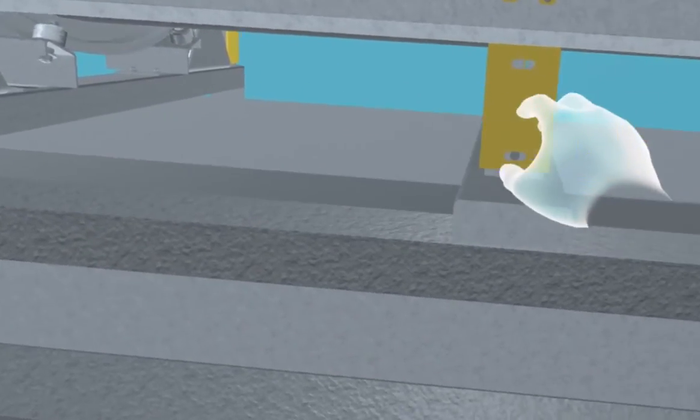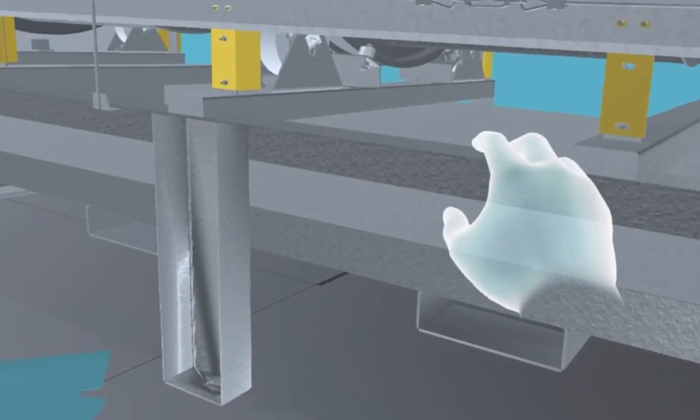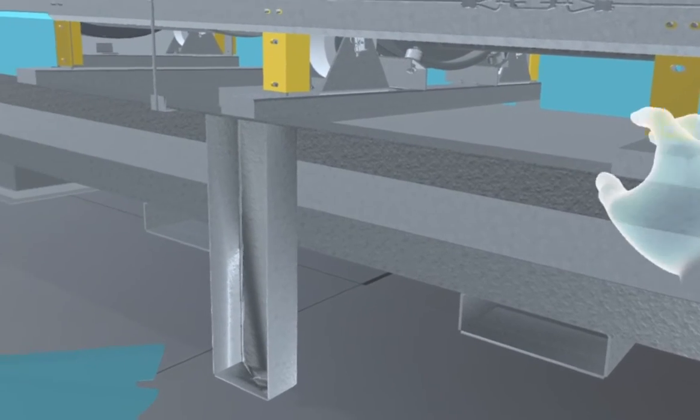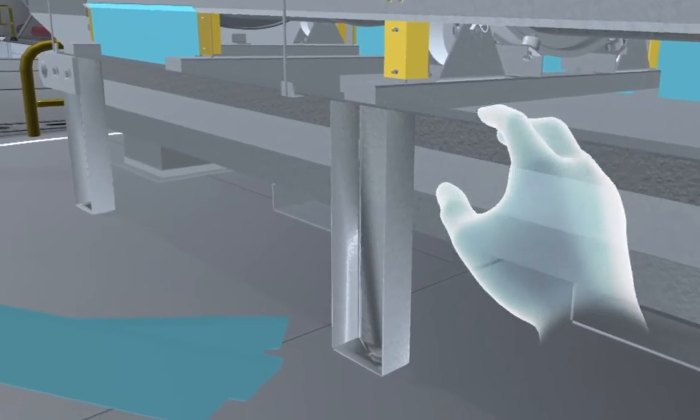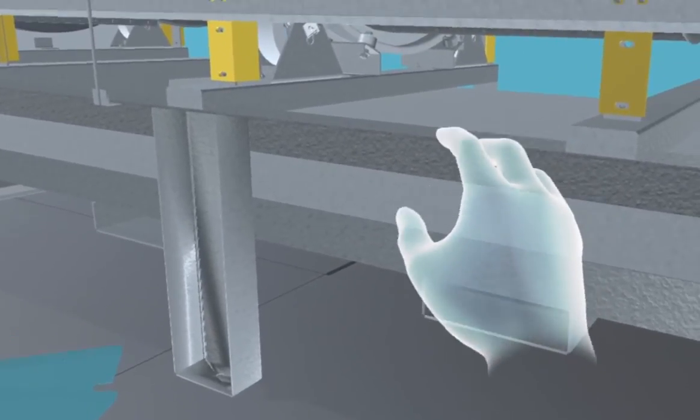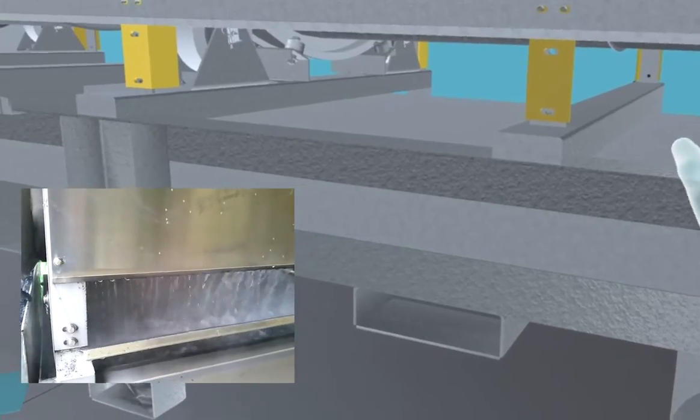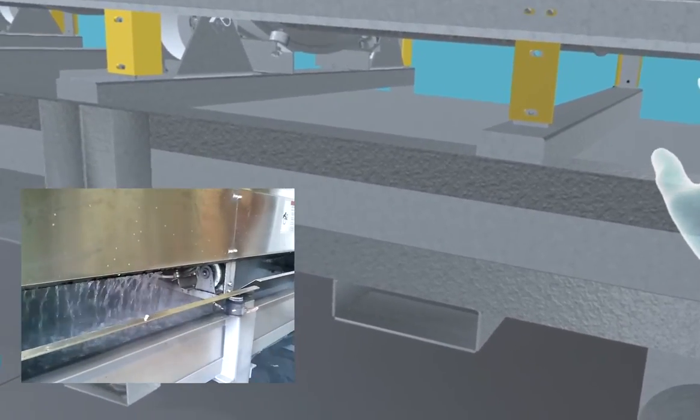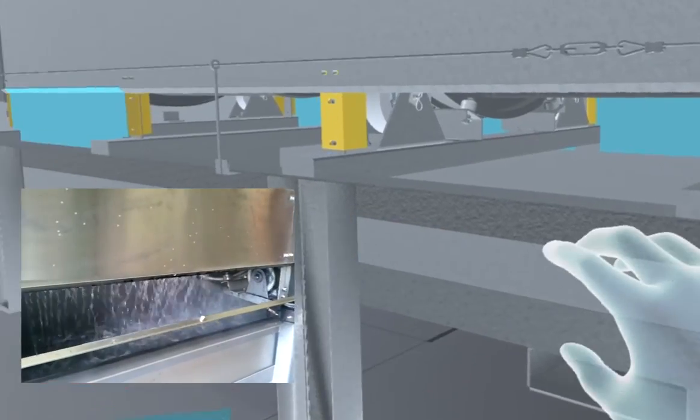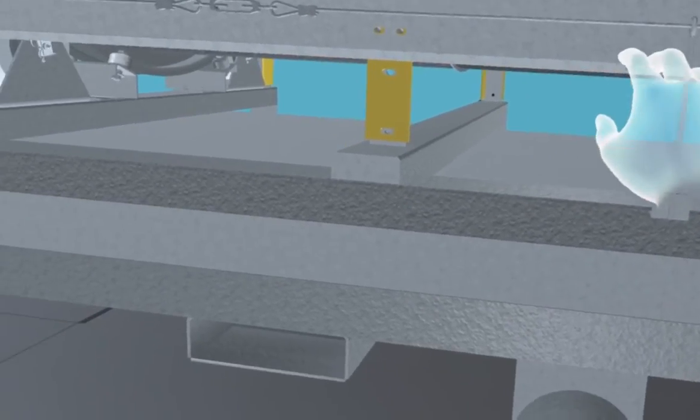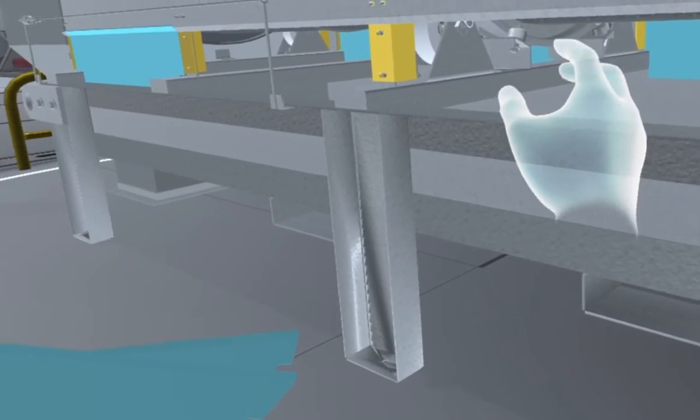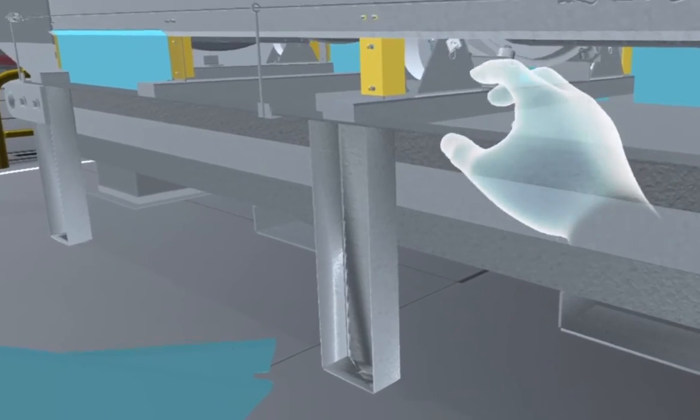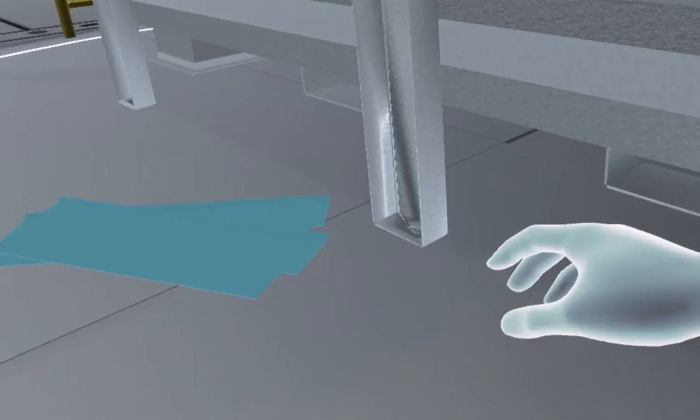And the other thing that you really want to have access to underneath the drum is to look at the filtrate. And the filtrate really tells you about how you're doing as far as polymer dosing. So if you're putting in a lot of polymer and you're not seeing a lot of filtrate come out, that means you're blinding. If you're seeing the filtrate be dirty where you can see solids in it, then you know you're under dosing the polymer. And this unit can easily reach 98, 99% capture rate. So this water is normally coming off crystal clear. And the other thing, as we mentioned, is most of the water is at the beginning of the drum. So you'll see a lot more water at the front than at the end. And that's when you see that cascade of less water going through the drum, that's when you really know you've nailed your polymer dosage.